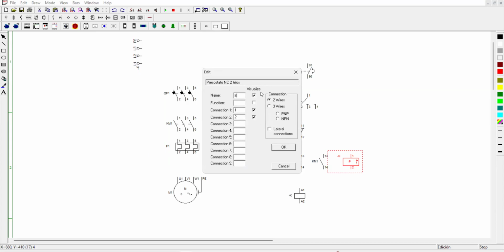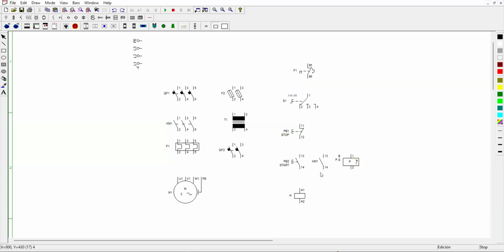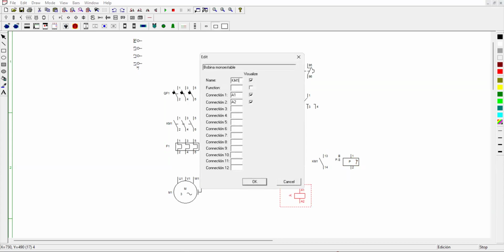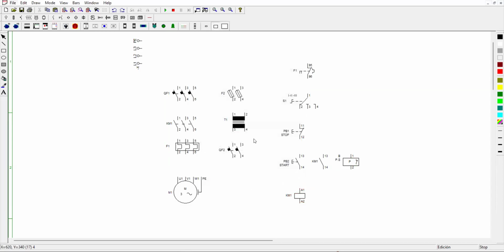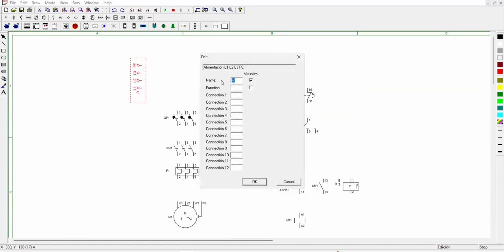The connection is two wire. I prefer to use a two wires connection. The three wires is what we call the normally open and normally closed contact. There is also a common contact. This is for the pressure switch. This is our magnetic contactor holding coil KM1. And that's it. We need to connect this to the source feeder.